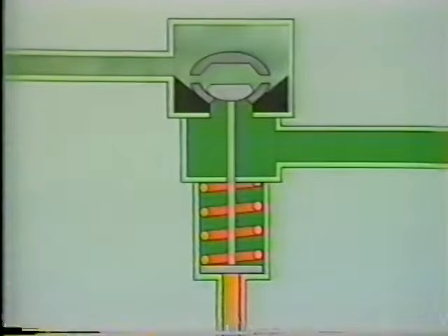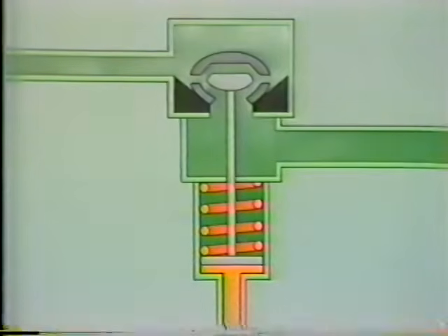The internal bypass valve consists of a valve disc and a valve seat. Also, holes are drilled in the main stop valve disc. As the valve stem is moved toward the open position, the bypass valve is lifted off its seat. This allows a small amount of steam to flow through the holes in the main stop valve disc.